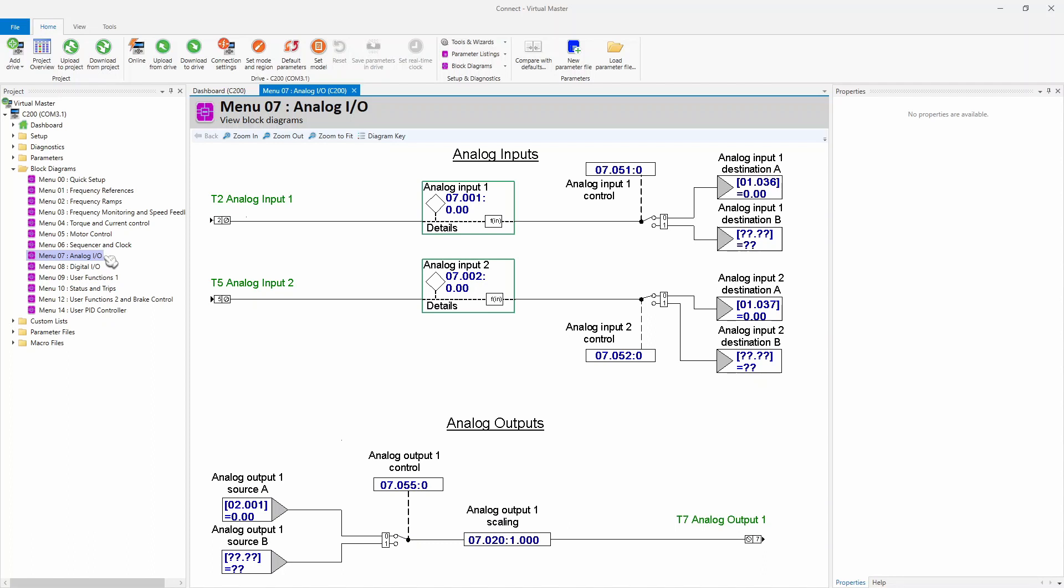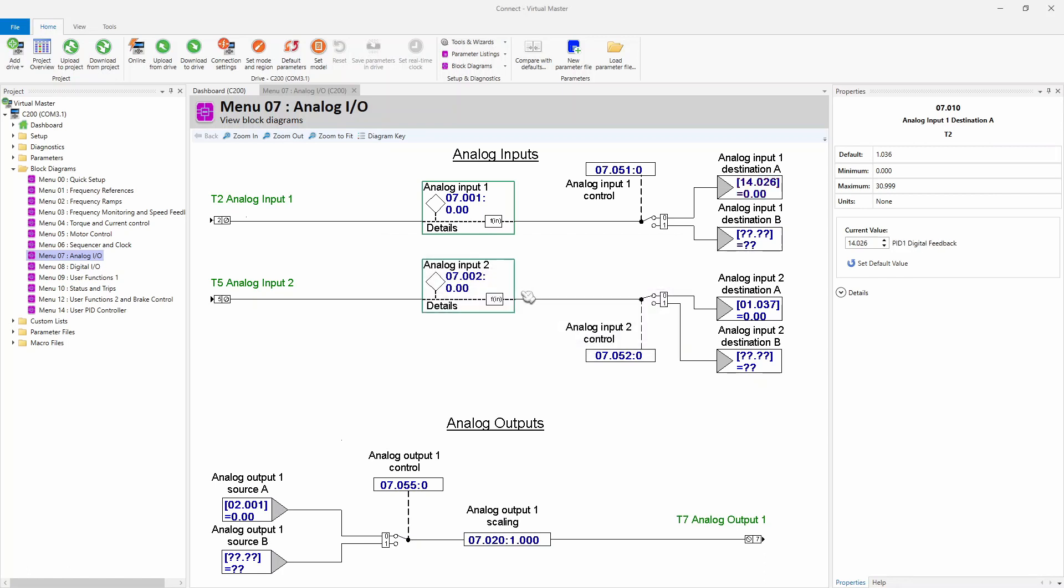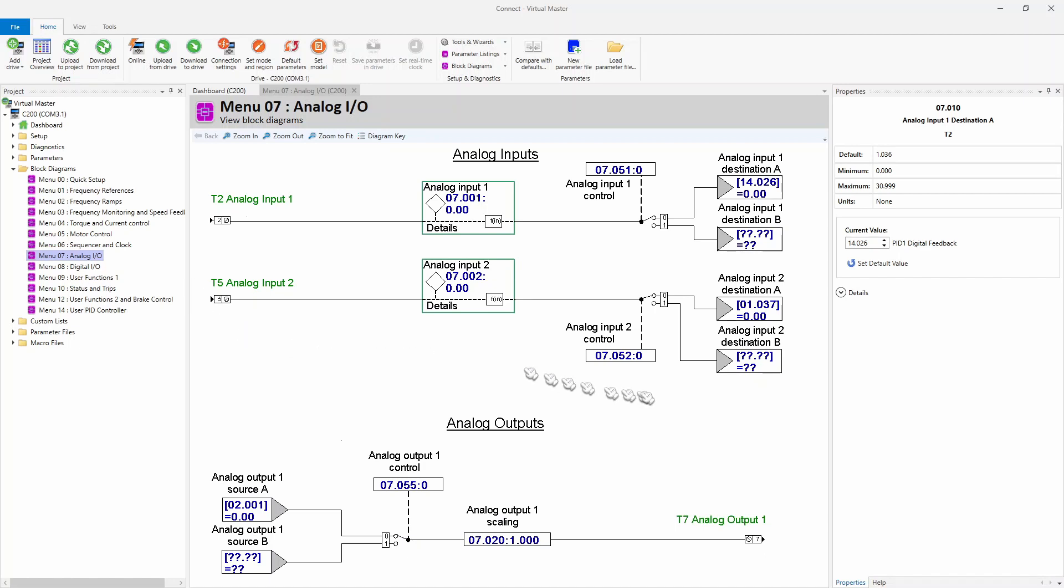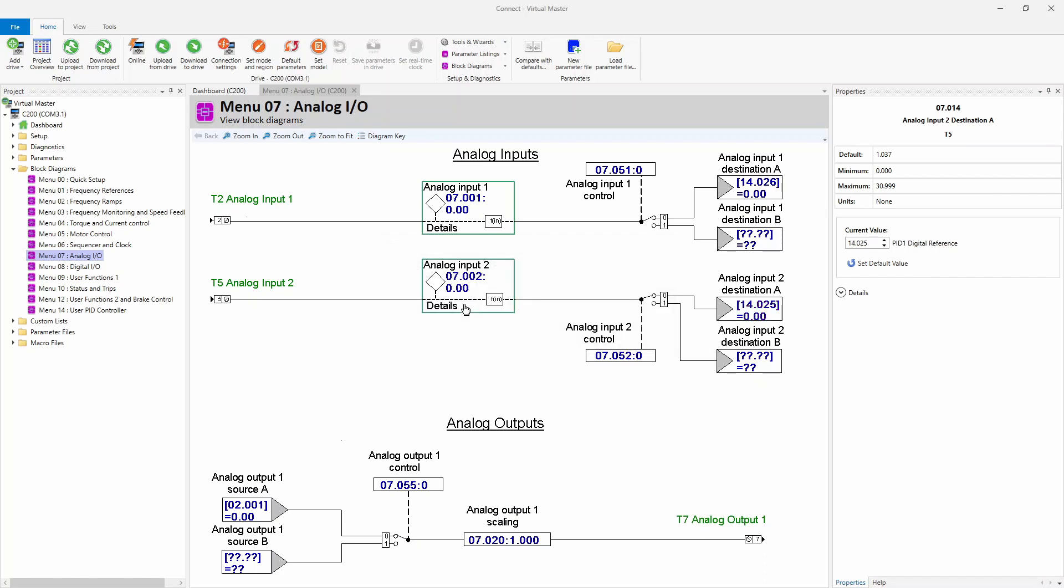So the first thing we're going to do is map the analog inputs to the appropriate locations of the PID block. Menu 7 is where we can find the analog inputs. The first analog input you see right here, we said we were going to connect it to our pressure transducer. And so we're going to send the destination of the analog input to 14.026. The second analog input we were going to use for our potentiometer. And we're going to set it to our PID reference. To do that, we're going to map it to 14.025.